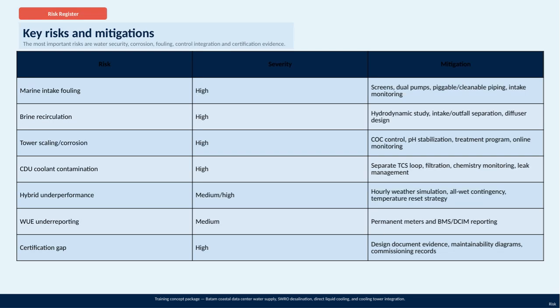Here we have an overview of the key risks associated with our project, along with their mitigation strategies. The main risks we're focusing on include water security, corrosion, fouling, control integration, and certification evidence. Starting with marine intake fouling, this risk is rated as high severity.